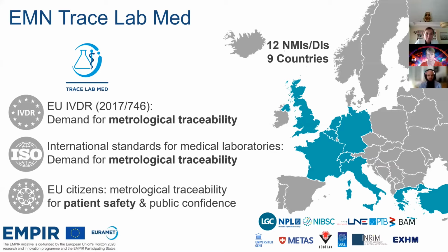It's a standard that is mandatory for laboratory accreditation in some European countries, and it requires laboratories to verify and document the metrological traceability of their measurement procedures. So this means that at the end of the day, they need to document the traceability, while the responsibility to ensure traceability and provide the respective information lies with the manufacturers. And they themselves can refer to the ISO 17511 to demonstrate traceability.